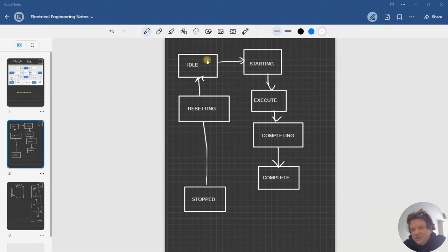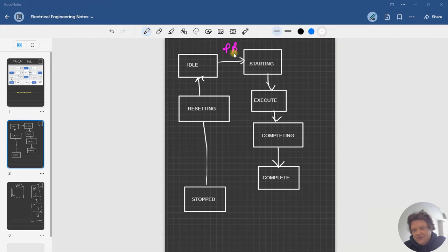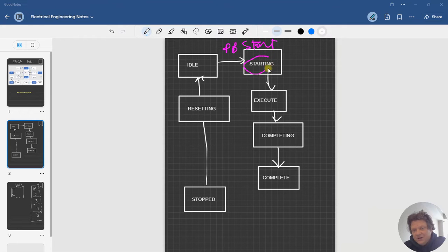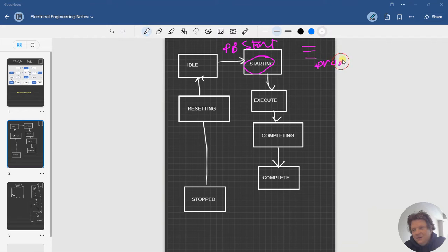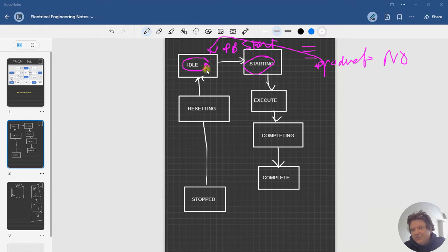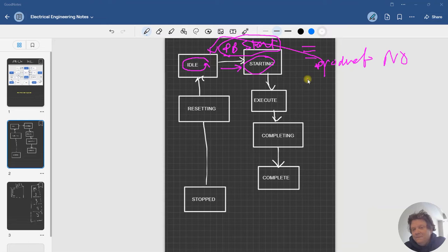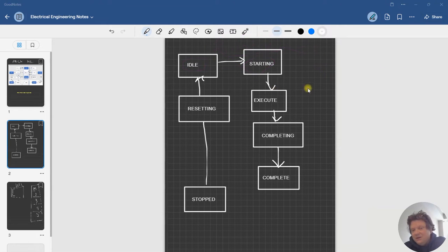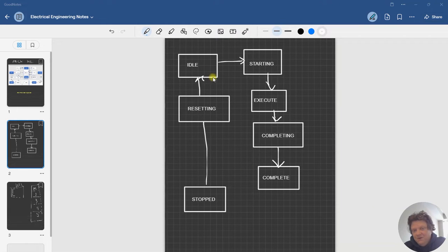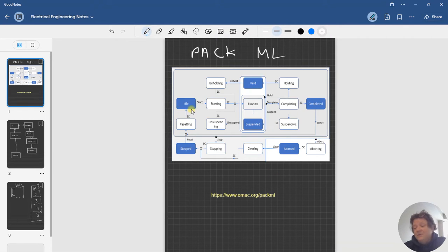At that point we may or may not be able to start the machine because maybe we don't have product. If I start the machine, push button start, and I come over here to starting, and then I go through my code and I get right here and I say do I have product, and it's a no, then I'm going to loop back to idle and I should hang out in here. I get product and then go back to starting, but I shouldn't have to come through and restart physically.